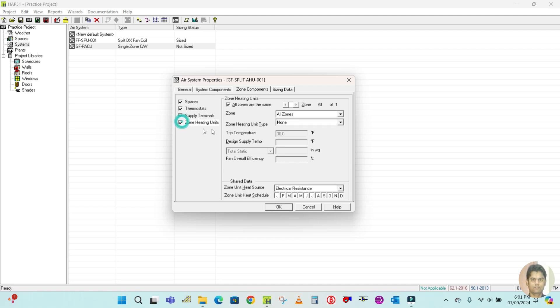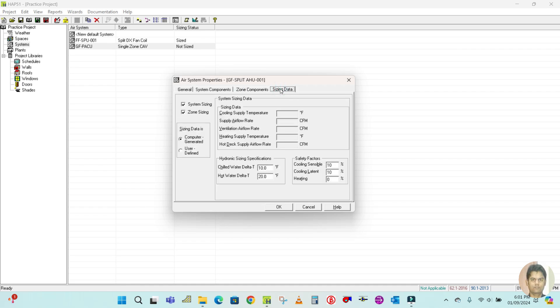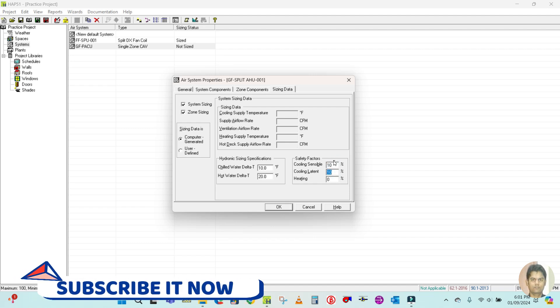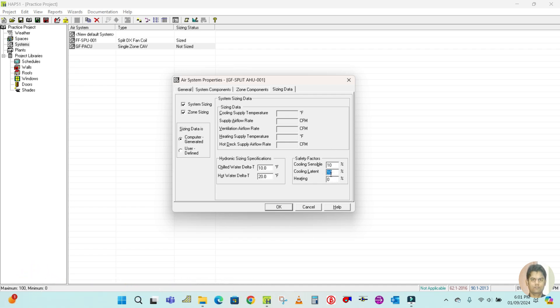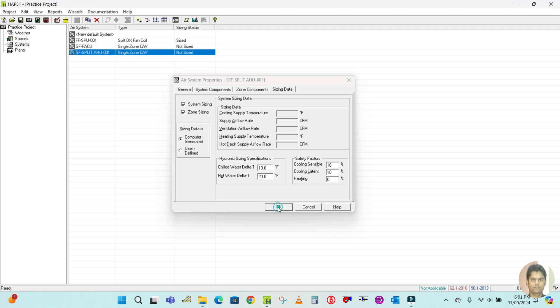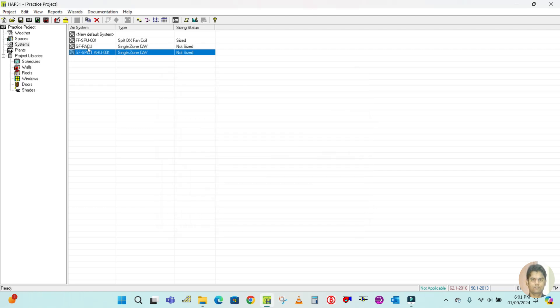You can enter all the heating information if needed. Then go to sizing data — do not change anything here, just enter the safety factor: 50 percent for cooling sensible and 10 percent for cooling latent. Then click OK.